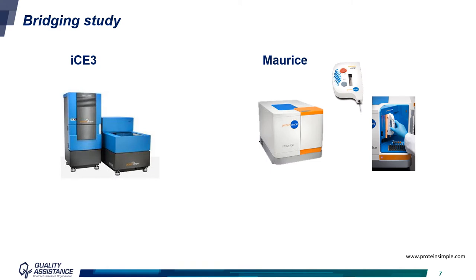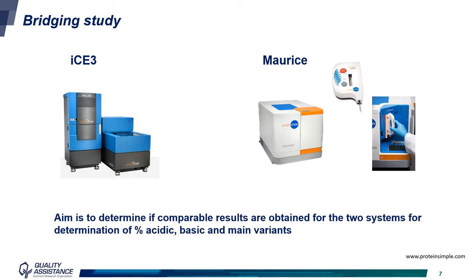Quality Assistance has several systems for ICIEF experiments to determine the charge variant profile of monoclonal antibodies. We have in the lab two iCE3 systems and two Maurice systems, commercialized by ProteinSimple. These systems are based on the same technology, but Maurice presents the advantage of using a built-in capillary, where only the cartridge needs to be inserted in the system — as you can see in the picture — without any capillary preparation or installation, and this improves the robustness of the analysis. The aim of the study we present here is to determine if comparable results are obtained on both systems for the determination of the percentage of acidic, basic, and main variants for monoclonal antibodies.